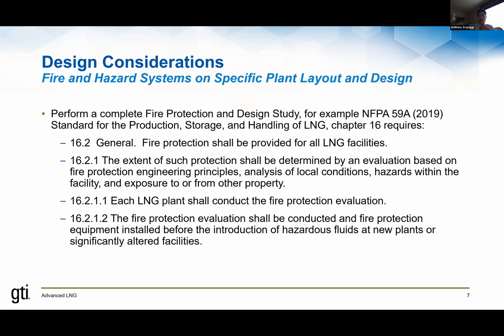It's a critical part of deciding where you put your components that do things like detect natural gas leaks, detect the concentrations of natural gas in a facility, and detect any form of ignition that might exist in the facility. There are smoke detectors, detectors that sense the change in temperatures, the rate of change in temperatures, and elements that can detect leaks by, let's say, a rapid decrease in temperature. Many different components are associated with the fire protection systems within the facility, and those are all the detection systems.